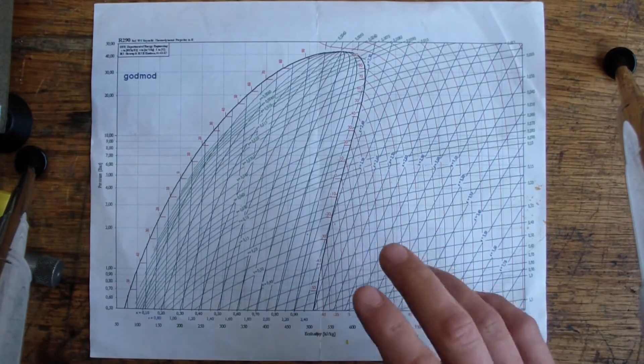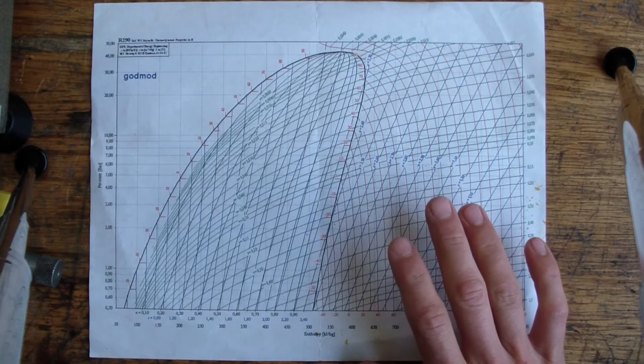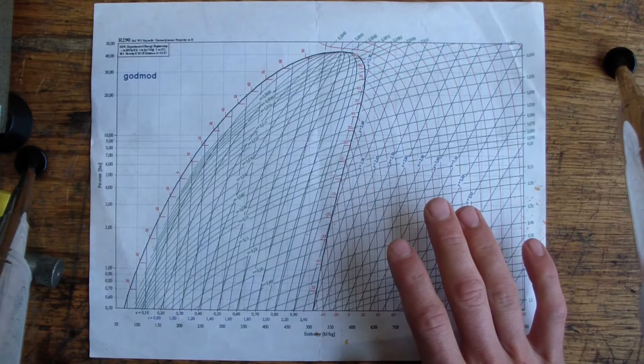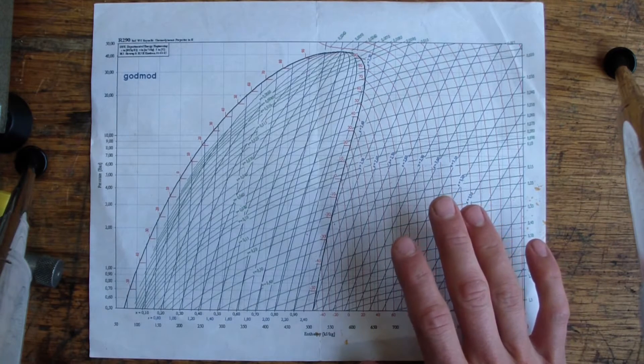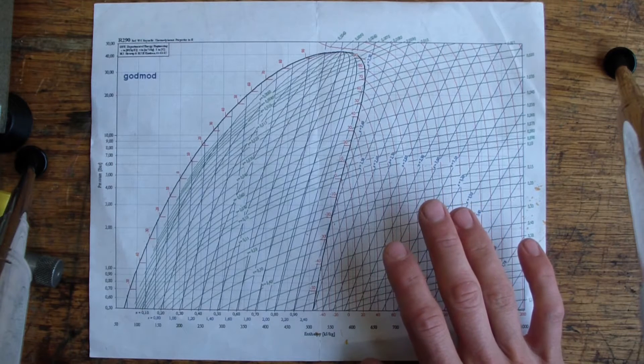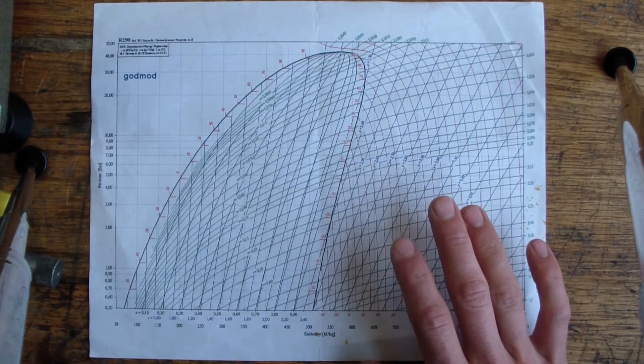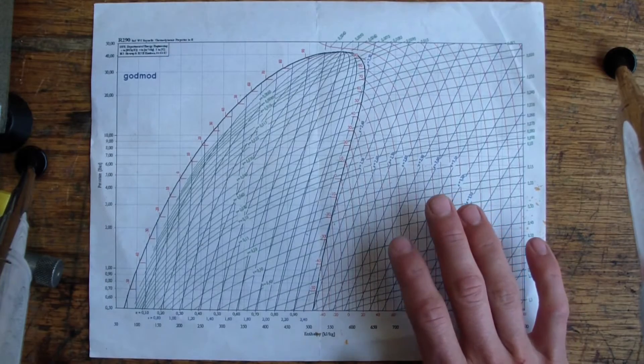Another option you might have is an automatic expansion valve. That's just a pressure regulator. The issue with a pressure regulator is it has a simple setting that you might be able to adjust to some certain extent, but it's not really going to cover the wide range of conditions that your system might be in. Now, if the characteristics of your system or the environment of your system don't change much, well then an automatic expansion valve might just work just fine.